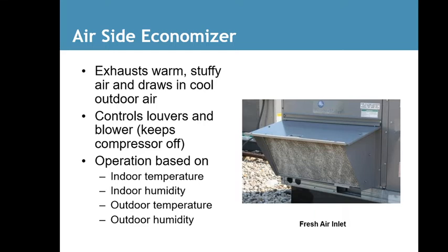So what you would do with an economizer is, let's say it's 80 degrees in the building, even though it's cold outside. Instead of turning on the air conditioning when the thermostat calls for cooling, the system checks a thermostat outside at the economizer that tells what the outside air is. If the outside air is 60, instead of turning on the air conditioner, it opens a vent. It sucks outside air in that is 60 degrees up off the roof and dumps it into the building. So instead of using the power of the large compressors in a commercial unit, it just turns on the indoor fan and circulates the air from outside to the inside.